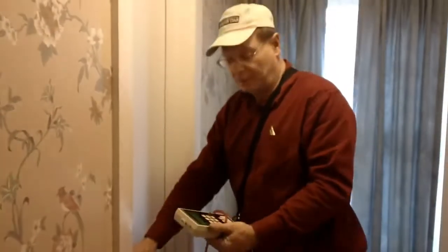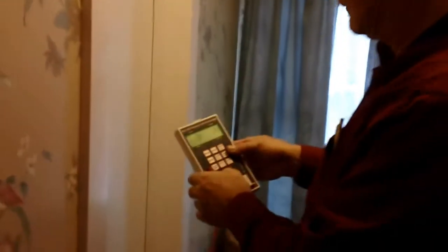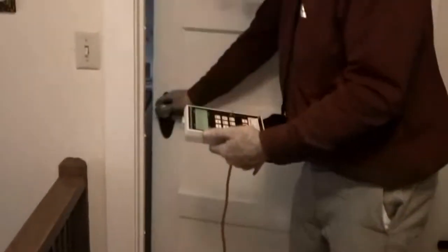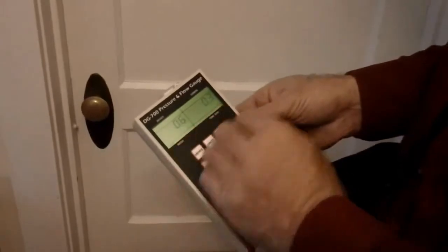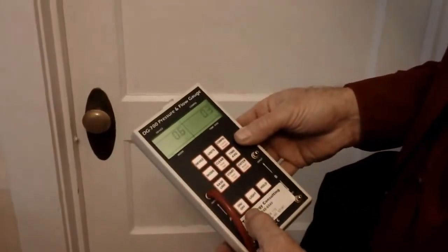We're putting a pressure hose in each room to see what the pressure effect is with our bathroom fans on or any exhaust fans in the house. This is also part of the audit when we're doing a combustion test on a boiler, a furnace, or a hot water heater that vent into a chimney. It's important to establish the pressures of these rooms in relation to the basement. We're measuring pressures again in each room as we work our way to the basement. And it tells us what the pressure difference is from room to room within the house.